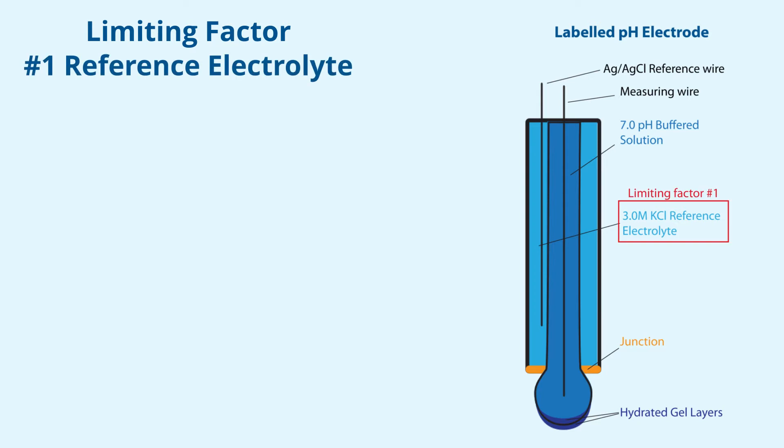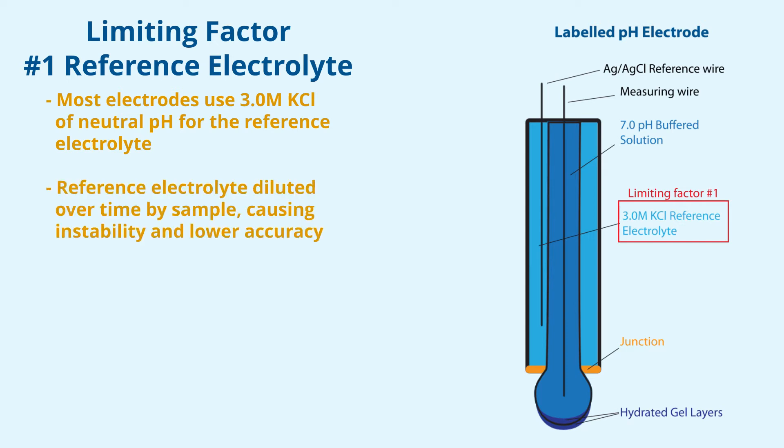One is the reference electrolyte. This solution is typically 3 molar potassium chloride of neutral pH and is exposed to the sample solution through the junction. Over time, the sample diffuses through the junction to dilute the reference which destabilizes the circuit connection.